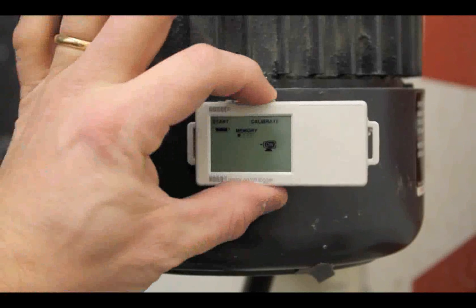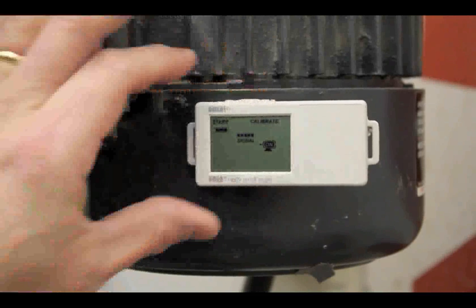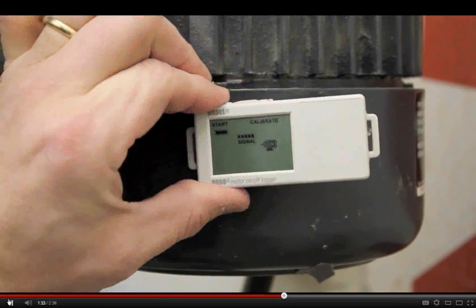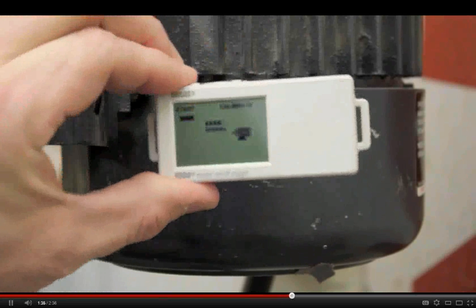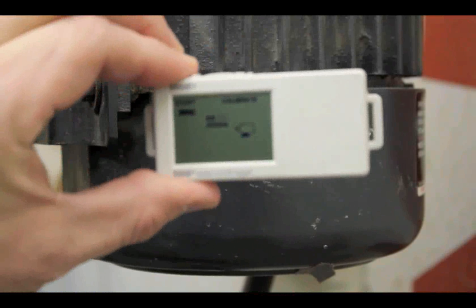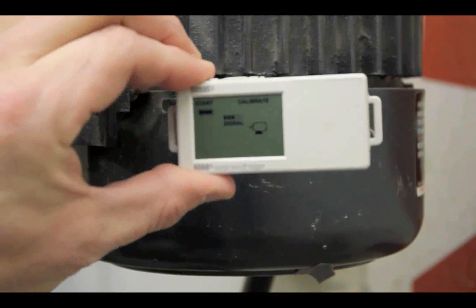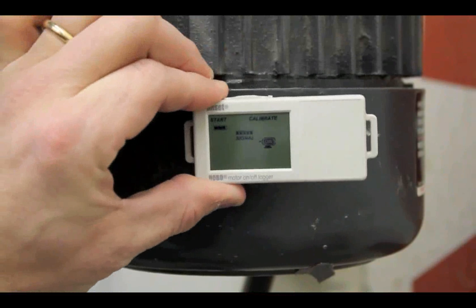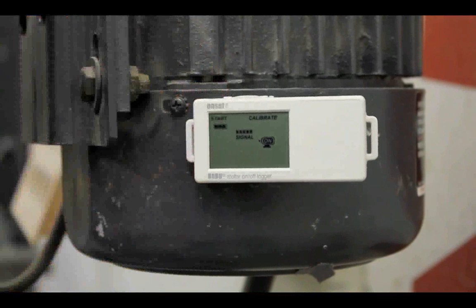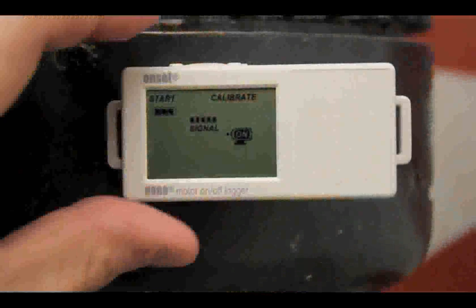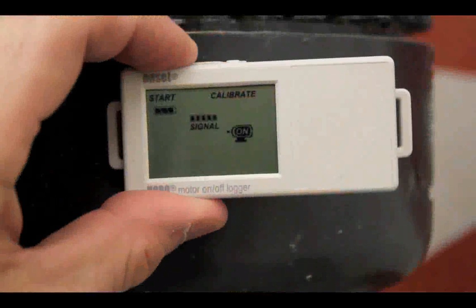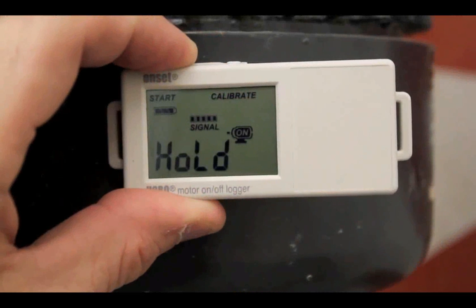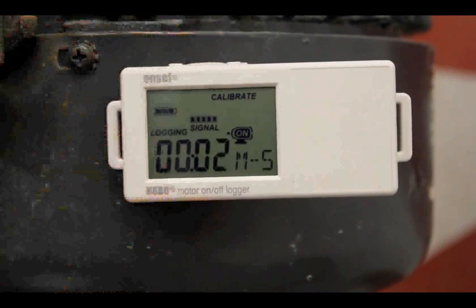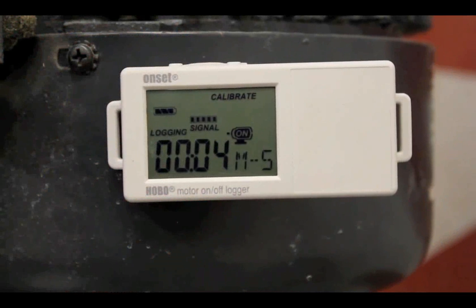We'll turn back over to the signal strength, and as we remove this from the motor, you're going to see the icon go to off. And as we get closer and we get back to that 5-bar mark, the logger will show full signal strength again. To start the logger, we're now going to push the button on the left-hand side and hold it down for 3 seconds. As you can see, you now have the logging indication on the icon, and your total runtime is now increasing in seconds and minutes.